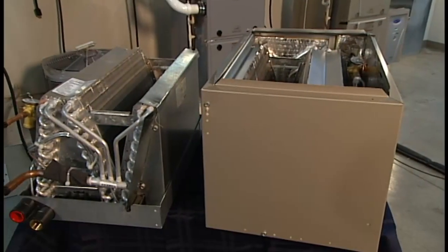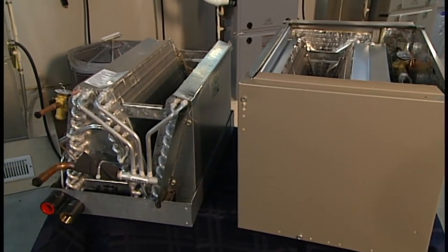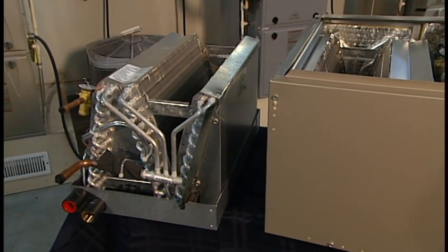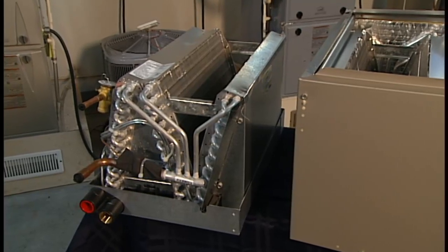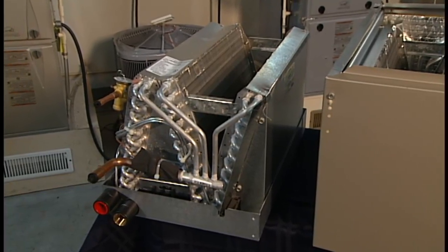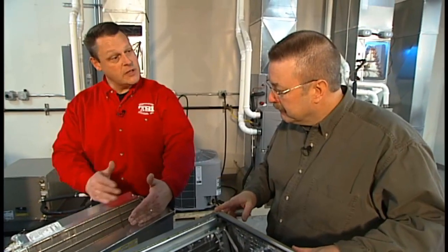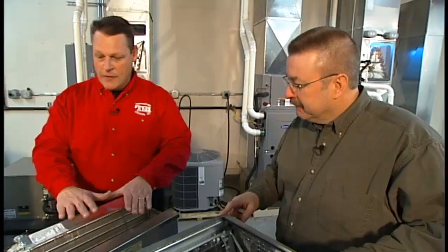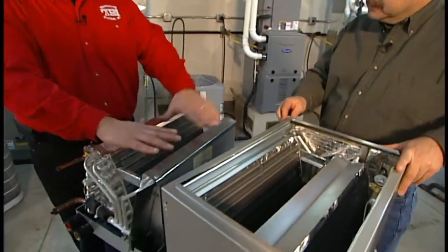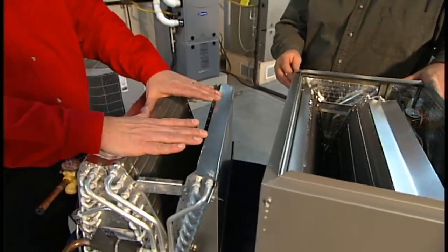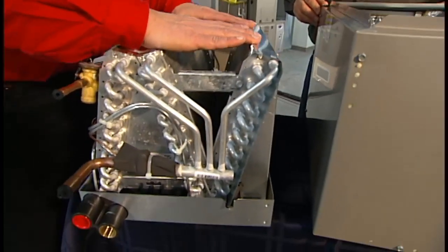Okay, you have some set up over here. They look a little different in shape, but are these also the coil? Yeah, these are still an evaporator coil like we looked at, but with today's efficiencies, we have to come up with a different configuration to give us more heat transfer surface to get a higher efficiency. This is an N coil. It happens to not have a casing on it because usually this is used for our retrofit market.